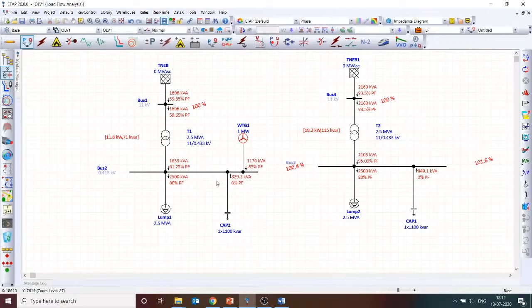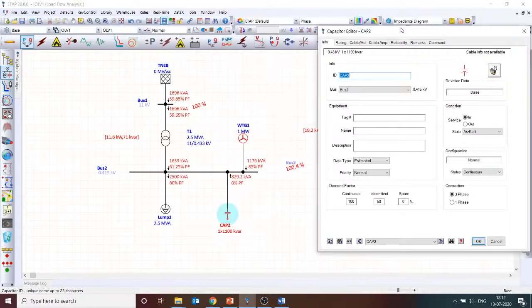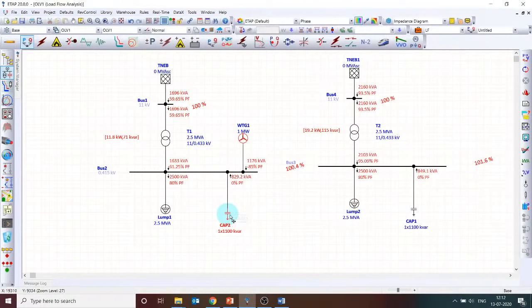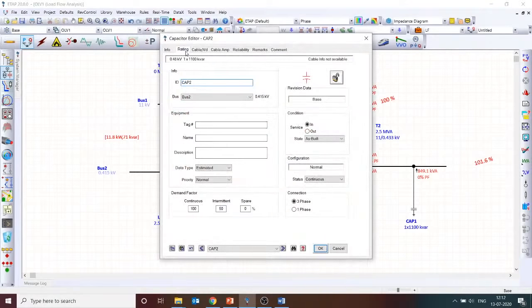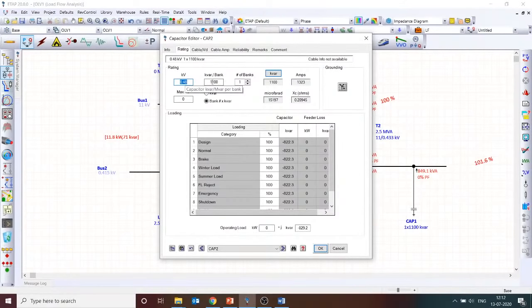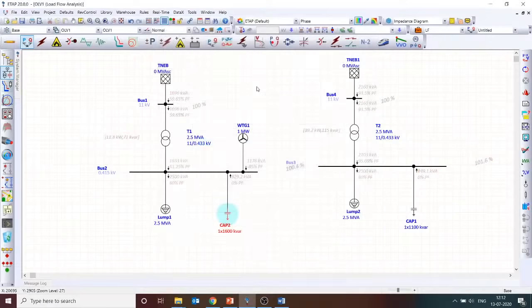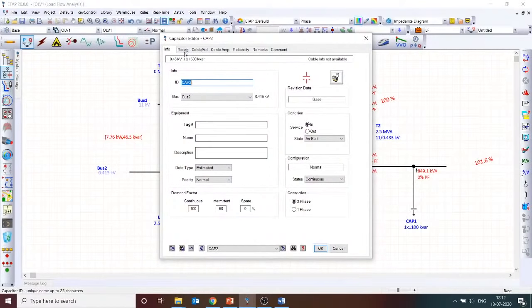So that means I need to increase the capacitor bank. Let me check what capacitor bank I need to put. Maybe let me change the capacitor to 1800 or something, or 1600. Let's see how the results change. I need to bring the power factor to at least 0.9 to eliminate the power factor penalty, am I right?